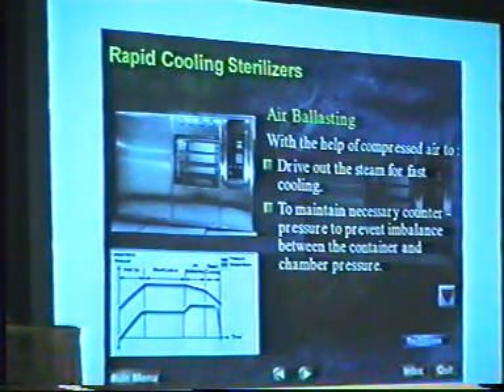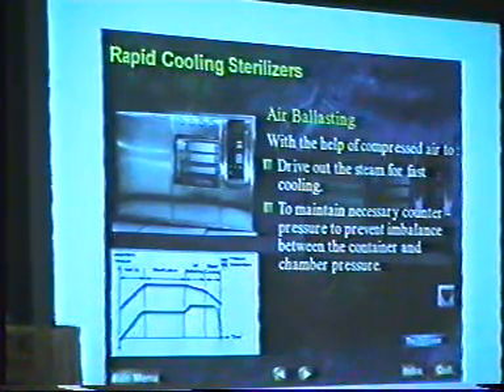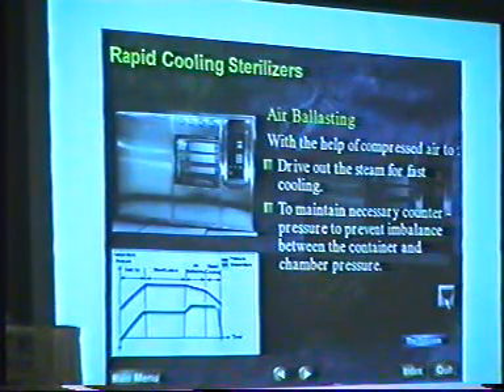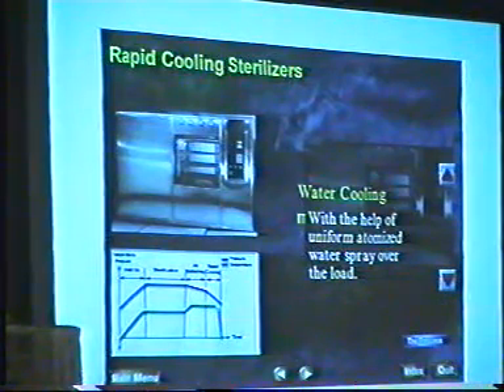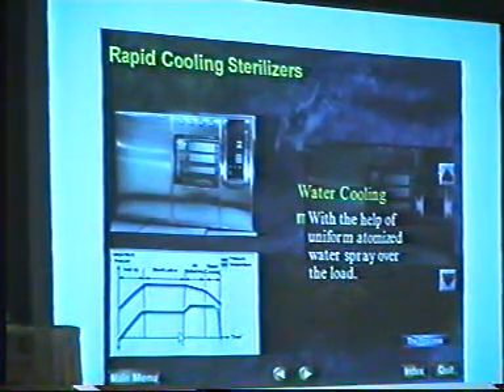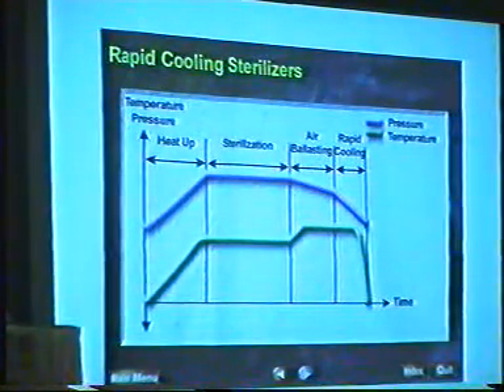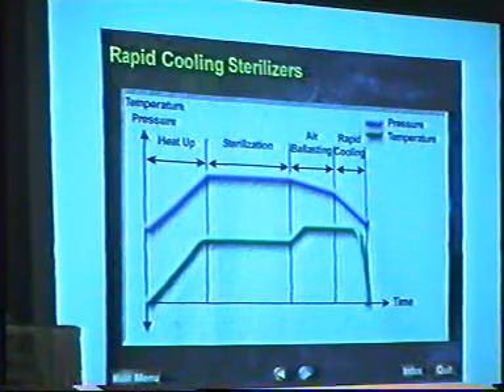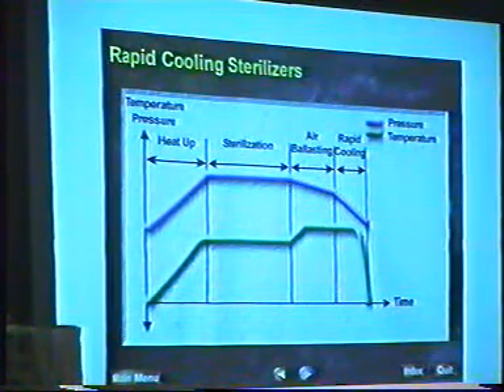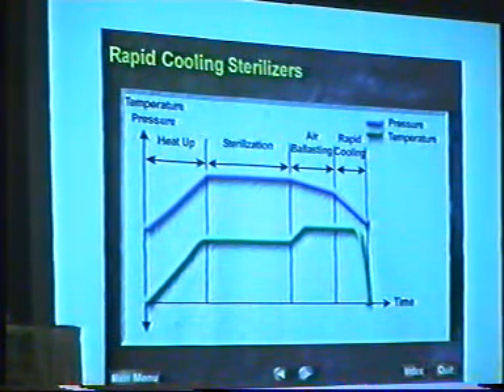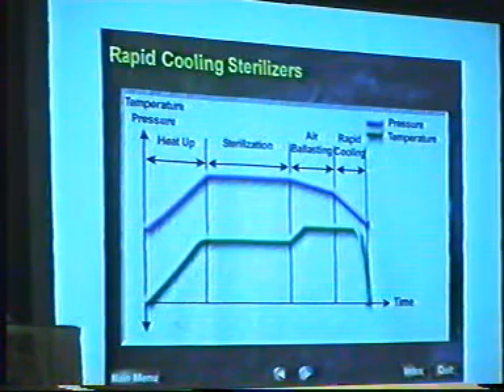Once you are sure that steam from the chamber is gone out, then you can have atomized water sprayed on the load, which will cool the load very effectively. And because of the air ballasting, there will be hardly any chance for any contamination to take place. However, this is not a foolproof guarantee.